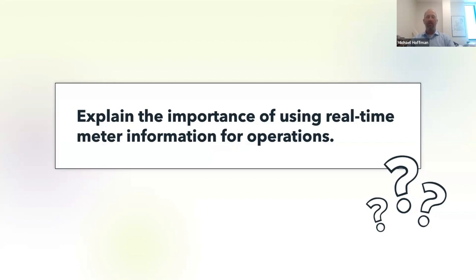So at about 1:15 in the afternoon, they're watching that real-time data and starting to what we call burn the ice. We can shut down as much as 2 to 3 megawatts of chiller power in favor of thermal energy storage, with the sole goal of controlling that real-time demand point. That serves us to the tune of between $500,000 and $1 million in avoided electric costs just by managing that demand every year.